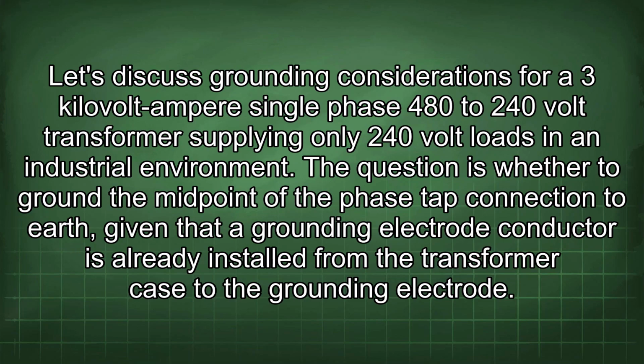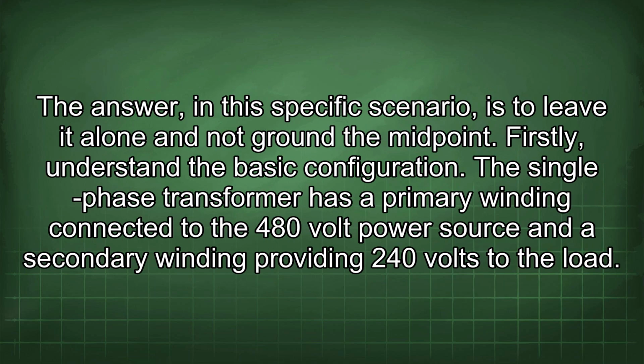Let's discuss grounding considerations for a 3 kVA single-phase 480 to 240 volt transformer supplying only 240 volt loads in an industrial environment. The question is whether to ground the midpoint of the phase tap connection to earth, given that a grounding electrode conductor is already installed from the transformer case to the grounding electrode. The answer, in this specific scenario, is to leave it alone and not ground the midpoint.